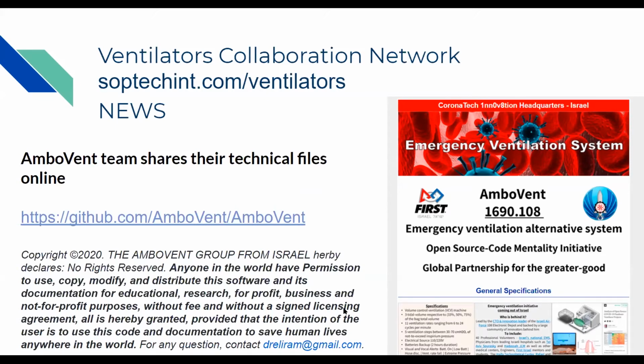But on the command and control system, the medical profession won't be able to accept me trying to change the parameters on the machine remotely, because when ventilating a patient, you want to see the feedback immediately, not to wait in a different room. So we are developing currently a command and control system that you'll be able to see all the feedback from the machine in a different room. And we have something that works so far. It's pretty basic.